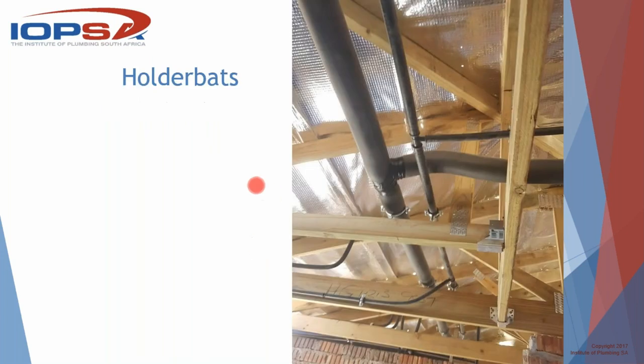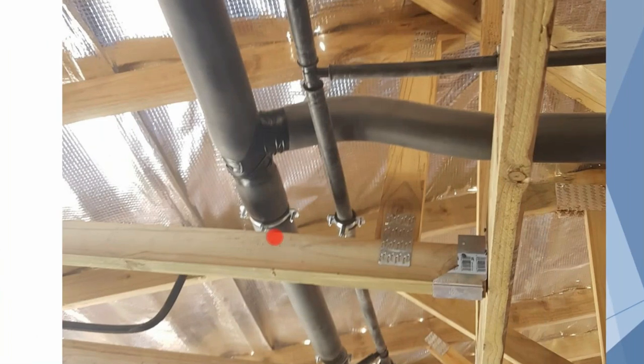There is another example of it. I'm going to just stop that there. I'm going to try and zoom in to that. And you see there that the bracket is completely over the lagging. If there's a worry about this not being secure enough, let's not talk about the frequency of brackets here, but we talk about that particular bracket. Is it secure enough to hold both the lagging and the pipe? And the answer is absolutely yes.